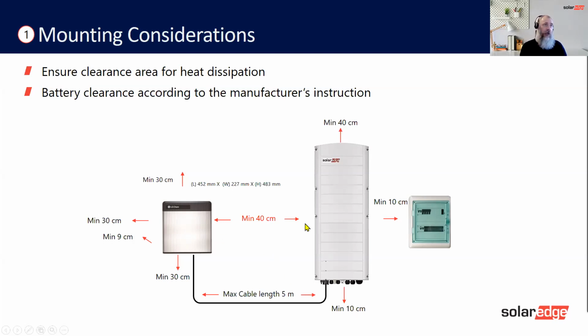Distance between the battery and the inverter is a minimum of 40 centimeters, but you must have a cable of 5 meters here. That's the most you can have. So maximum cable length is 5 meters. This is the DC side, okay? DC side.